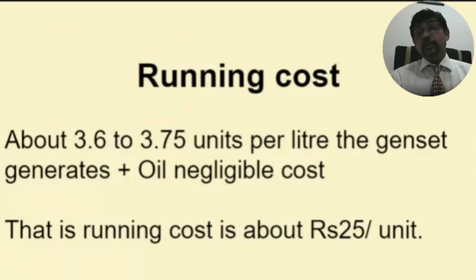The generation of 3.6 to 3.75 units also depends upon the quality of filters in the generator. If the filters are not cleaned, then the flow of diesel is not going to be uniform. So the diesel line is not going to supply the right amount of diesel in the cylinder where the combustion takes place. With the combustion not taking place properly, a customer can say, okay, we are running the generator, but it is not giving us more than 3.2 or 3.1 units, because the filters are not cleaned. So timely maintenance, that is changing of filters, is very much important.